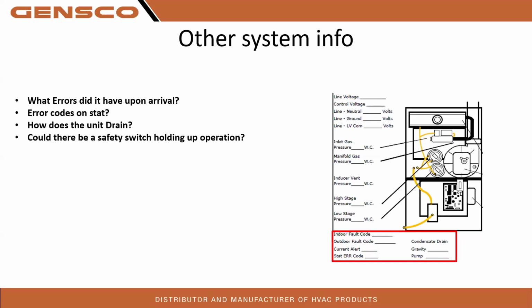So a lot of the times when guys call in a tech with those 2 error codes at the thermostat, especially variable, that's the first thing we'll do, send them to the outdoor unit. Let's start writing down the outdoor unit codes, right? Because we can find commonalities and failures. Oh, look, it has a bunch of dome sensor hits, or we have compressor derates because of a sensor issue or a charge issue. So we can really break down, write them all down, write everything you can down.